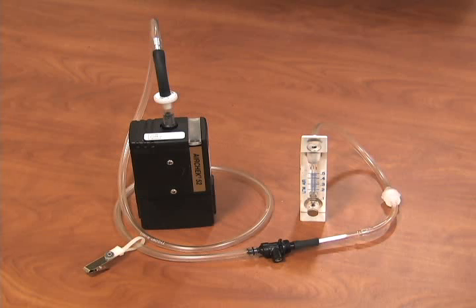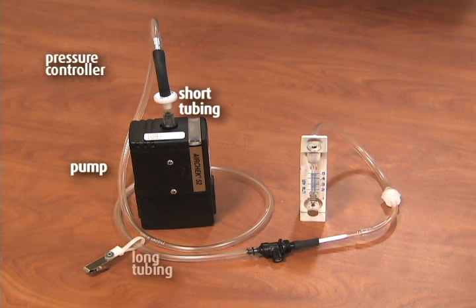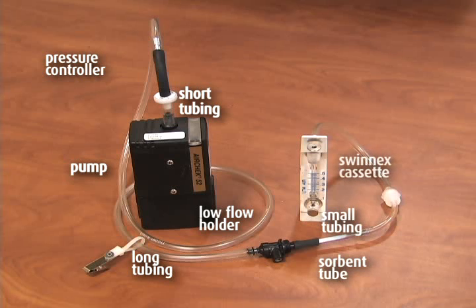The order of the components for calibration is pump, short length of tubing, constant pressure controller, long length of tubing, adjustable low flow holder, sorbent tube, small piece of tubing, Swinnex cassette with filter, and rotameter.